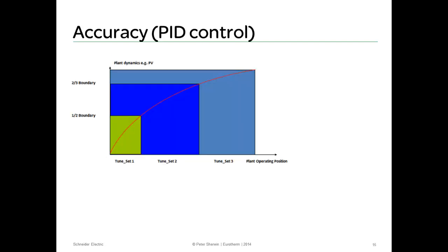Generally, the 0.1 to 0.2% accurate instruments also come with advanced control strategies including multiple PID sets. This helps you accurately tune a furnace that has different personalities at different temperatures. For example, an oven with a single burner for low temperatures and multi burner for high temperatures - the control characteristics will change with temperature. Vacuum furnaces with low temperature convection heating compared to high temperature radiation heating will require different PID constants to give the most accurate performance.